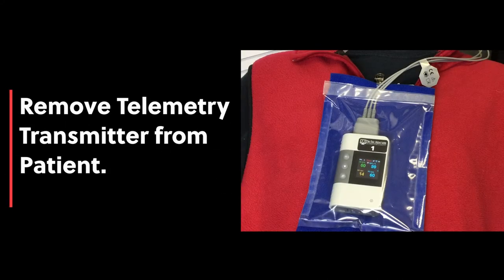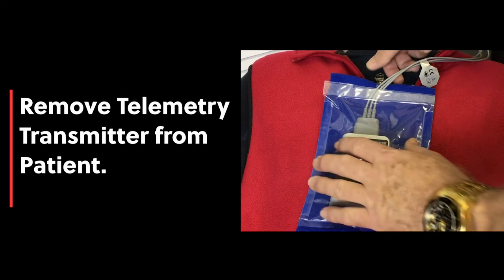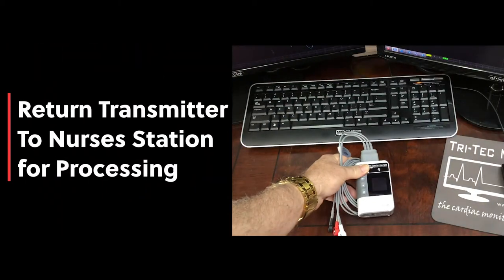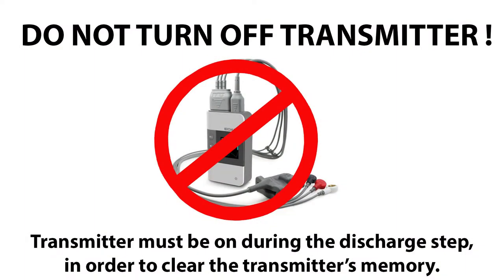Step 1. Removal from patient. Remove the telemetry transmitter from the patient. Now, take this transmitter back to where the MFM-CMS central station is located for processing. Important. Do not turn the transmitter off at this point. The transmitter must be left on during the discharge process in order for all data to be transferred to the database and erased from the transmitter.